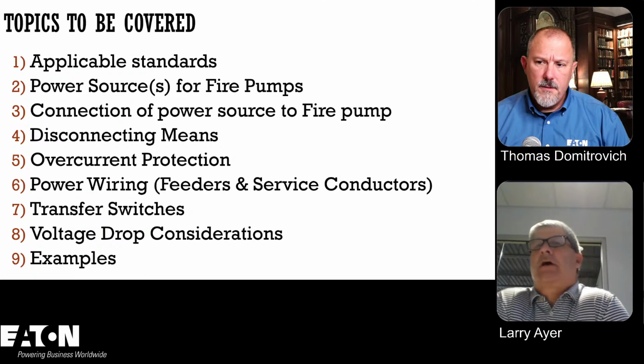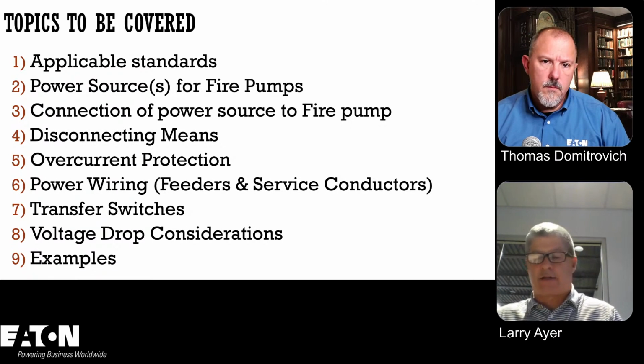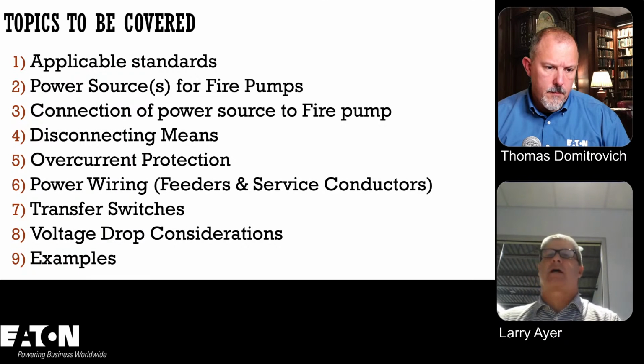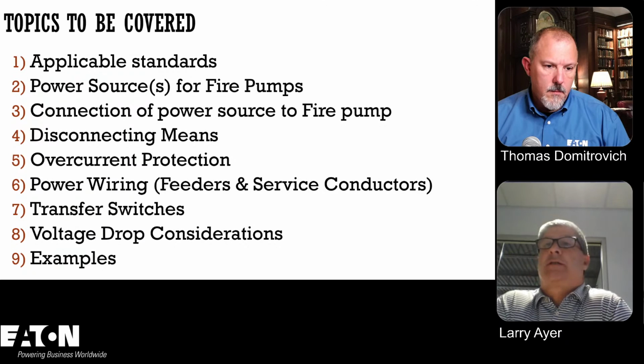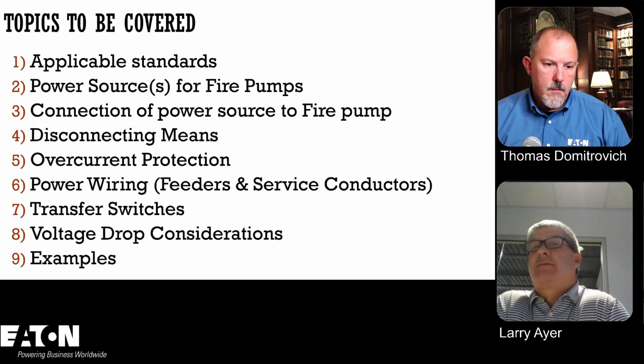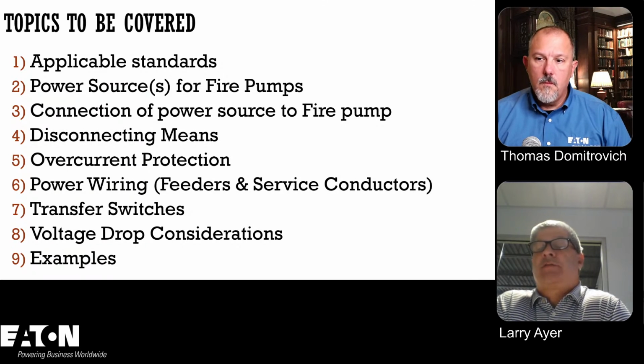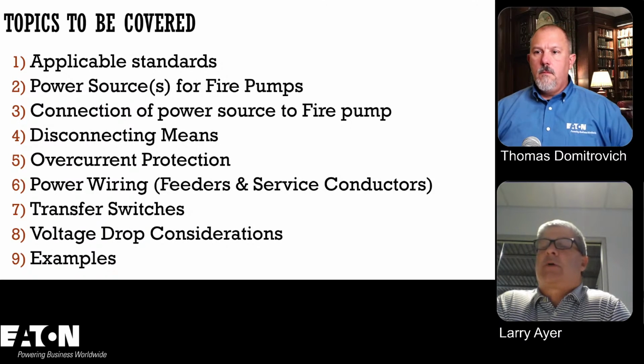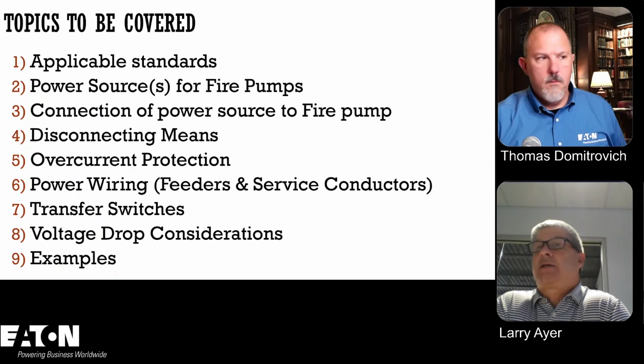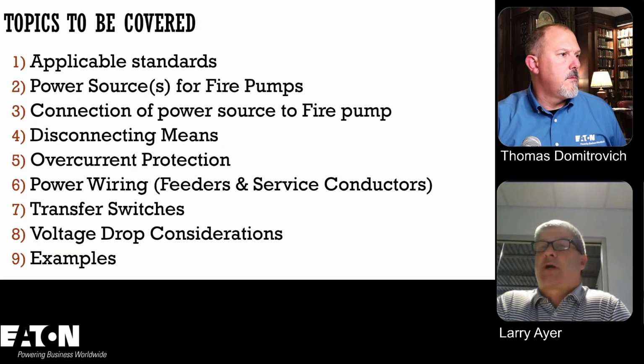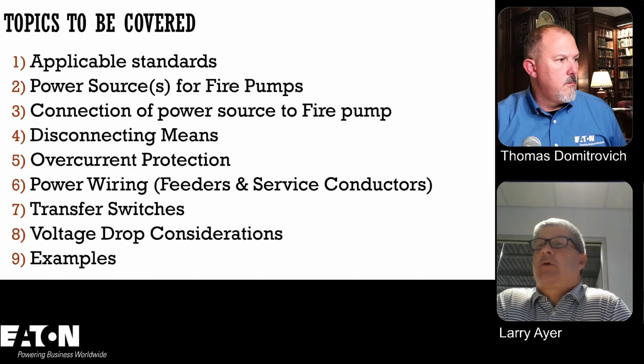This is my guess at it, but a lot of times you see these enclosures in the basements. You see them in these fire pump rooms that maybe don't get much maintenance. There's a lot of dirt buildup. Maybe you have the situation where, when the fire pump is called on, you want to make sure that this fire pump operates at any cost. So you might have pressure on the fire pump, you might have a leak in the room, so you probably want that NEMA 2 enclosure. You want that enclosure to be a little bit more beefy than your standard NEMA 1 enclosure. So that's what I would think.